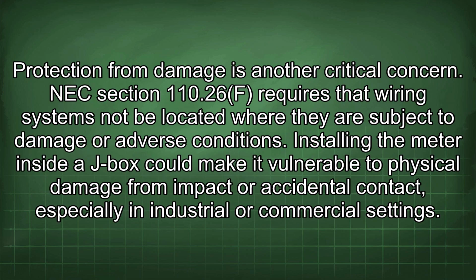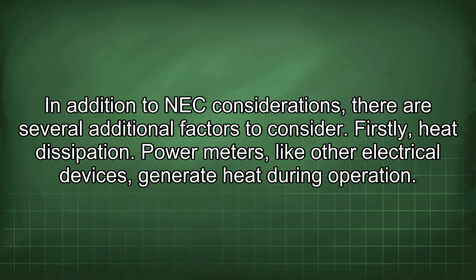Protection from damage is another critical concern. NEC Section 110.26F requires that wiring systems not be located where they are subject to damage or adverse conditions. Installing the meter inside a J-box could make it vulnerable to physical damage from impact or accidental contact, especially in industrial or commercial settings. In addition to NEC considerations, there are several additional factors to consider.